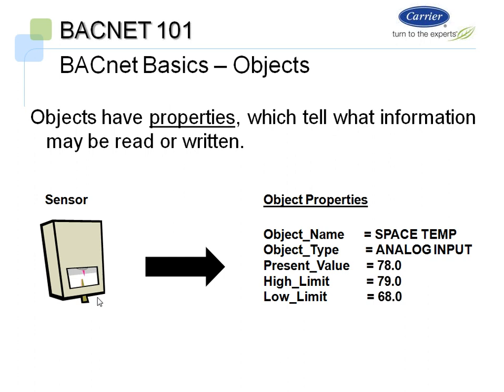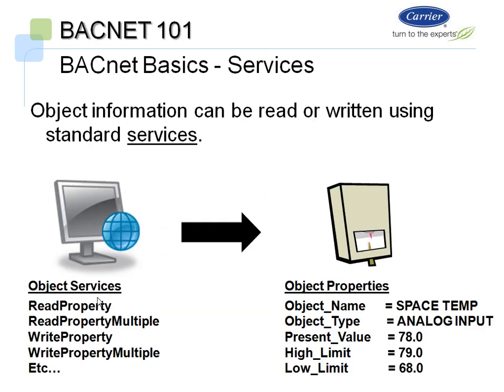So in order to access a specific point via the BACnet, you would reference it via its object name, and you would read its present value or write to its present value, depending on how you wanted to access it. And reading and writing are part of the next rule of BACnet, which is the services rule, or regular standards of BACnet. So there are a couple different services. The main two services that you would use would be a read or a write service. This is how you integrate points and access points throughout the control system.